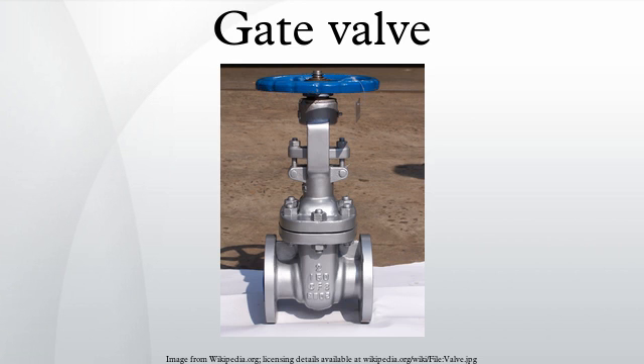For extremely thick fluids, a specialty valve often known as a knife valve is used to cut through the liquid. On opening the gate valve, the flow path is enlarged in a highly non-linear manner with respect to percent of opening. This means that flow rate does not change evenly with stem travel.